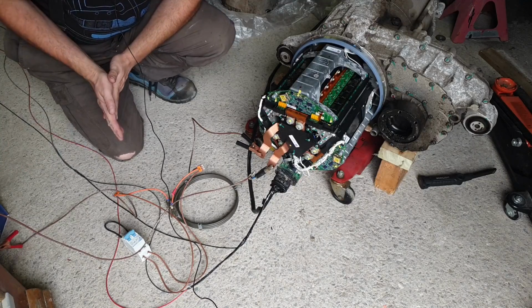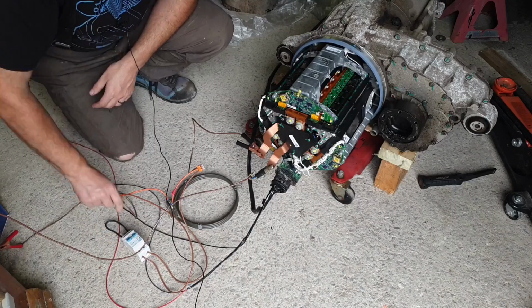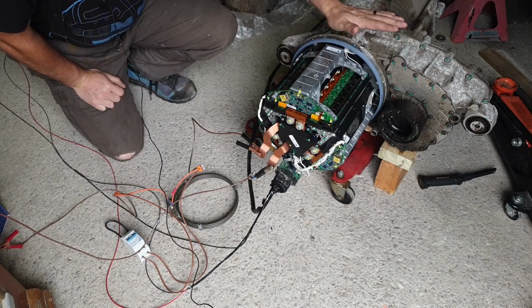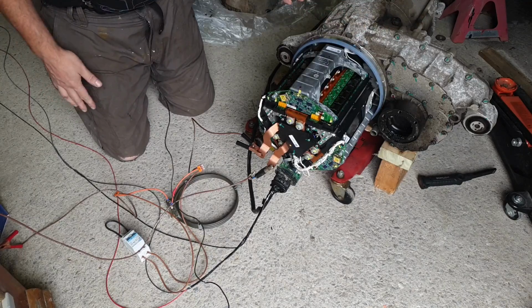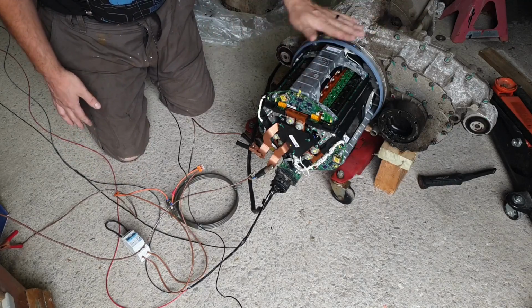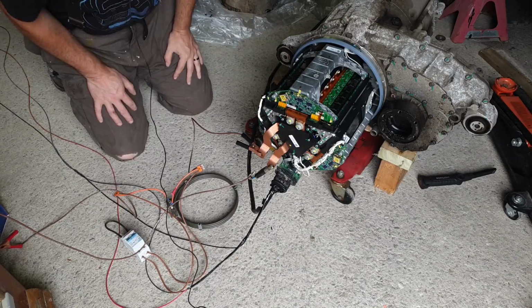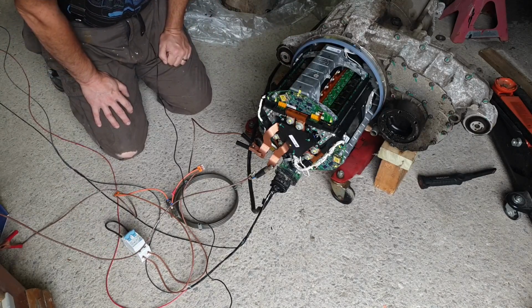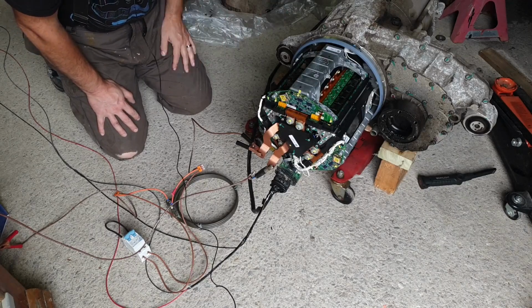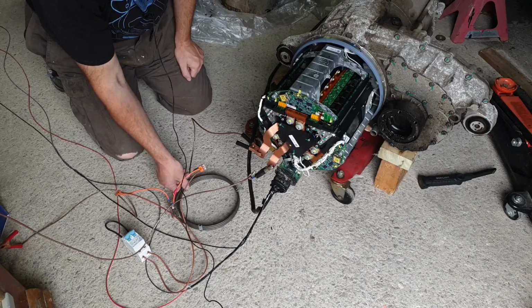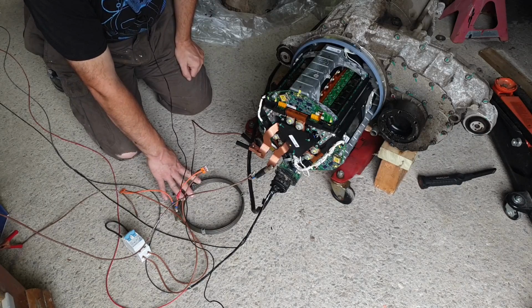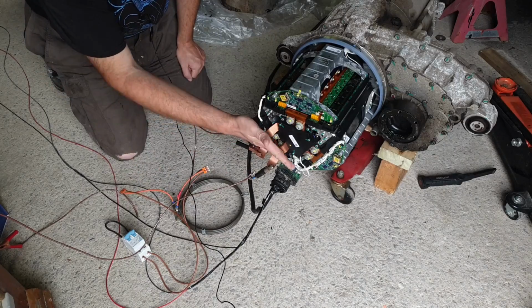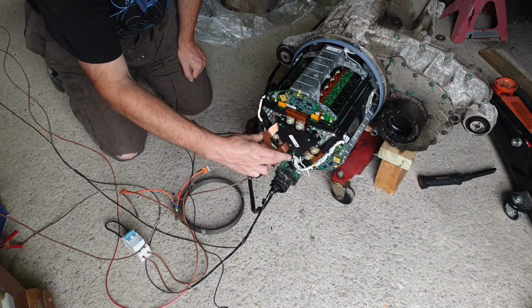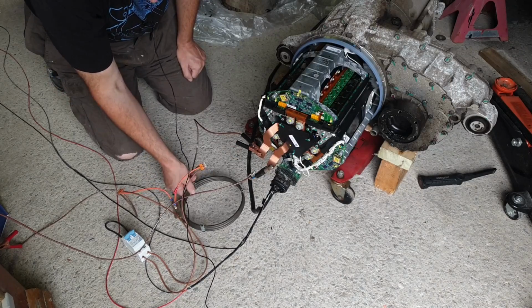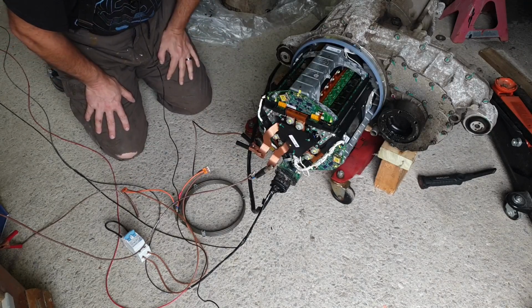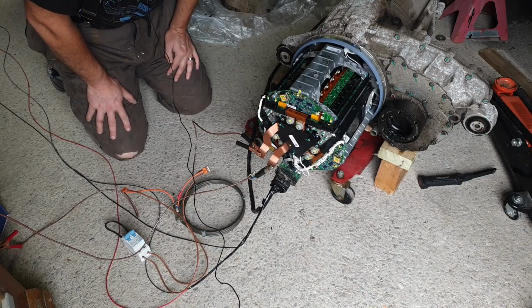Once everything is powered up and we're ready to run, I'll just close the circuit breaker. If something abnormal occurs and our drive unit tries to draw more current than the circuit breaker allows, it's going to pop off. Our motor could be turning, not turning, jerking around, whatever - but the heating element always remains in circuit. So any energy that needs to come out of these bus bars can pass through that heating element and back into our test voltage supply. That's the critical thing to keep in mind, folks.